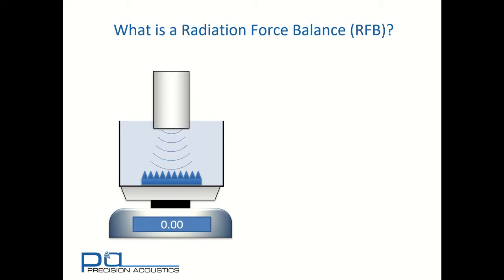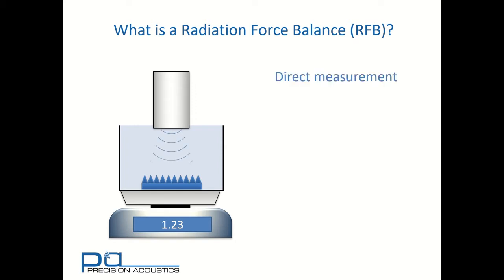We arrange for an ultrasonic transducer to be configured so that its field radiates onto the target. When the ultrasonic transducer is switched on, there is a momentum exchange that occurs when the ultrasonic wave encounters the target. This is translated as a downward motion and therefore perceived by the balance as an effective mass. Please note that this is a direct measurement. There is a direct relationship between the ultrasonic power and the effective mass perceived on the balance.